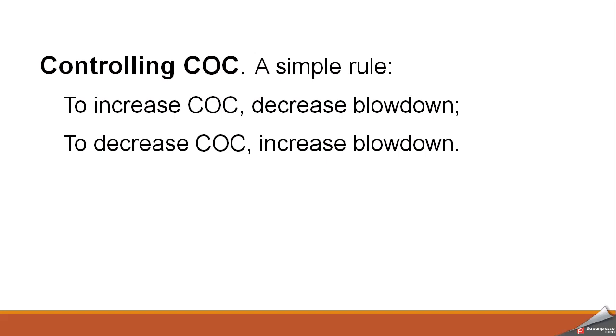But very simply, if you increase the blowdown, this will decrease the cycle of concentration. If you decrease the blowdown, this will increase the cycle of concentration.